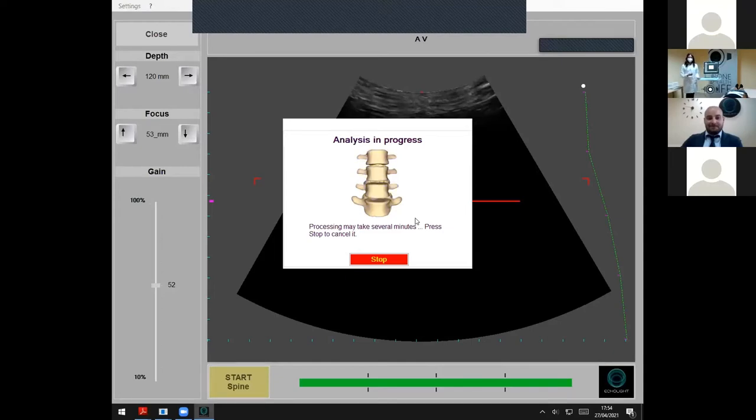As we said, R.E.M.S acquisition is not based only on the analysis of the image, but on the signals coming from the bone. Artifacts due to the patient's respiration, or for example, the presence of artifacts on the spine, such as calcification, osteophytes, and so on, will result in a spectrum that does not match in any way with the one of reference given by the bone itself, and the algorithm will directly discard it, taking it out from the analysis. This means that the result that you're going to get with the R.E.M.S scan is going to be a precise value that is dealing only with the content of bone related to the examined tract.